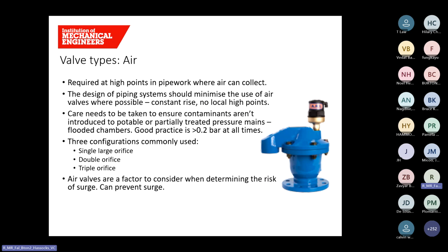Valve category is air valves. Air valves are needed at high points in pipework where air can collect. The design of a piping system should minimise the use of high points and air valves, but sometimes they're unavoidable. When selecting air valves for potable water applications, it's important to consider the potential for contamination. So, for example, where surge or low pressures can occur, the air valve can actually draw in contaminants from outside, such as from flooded chambers.